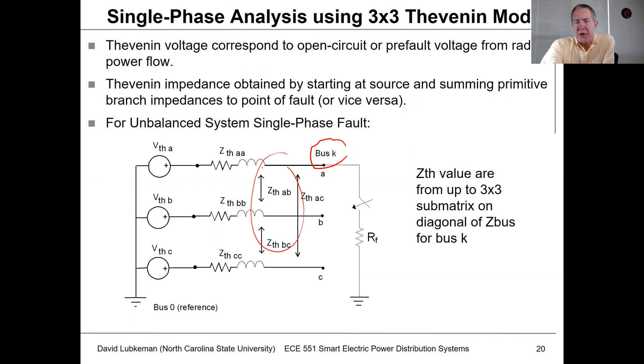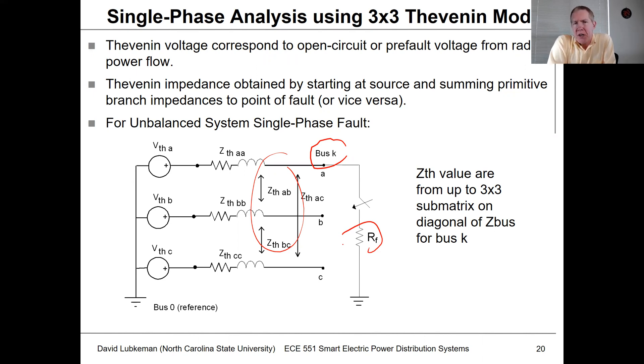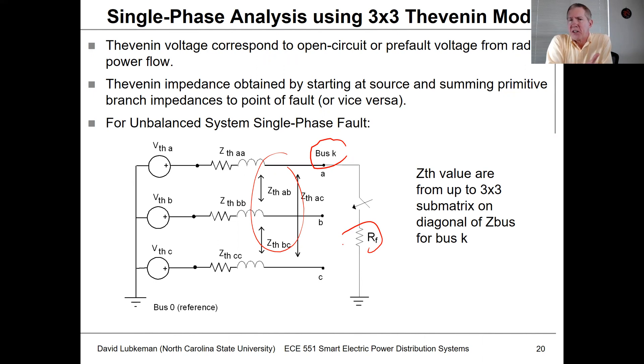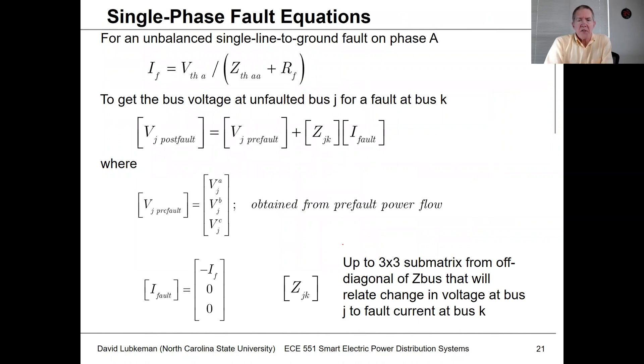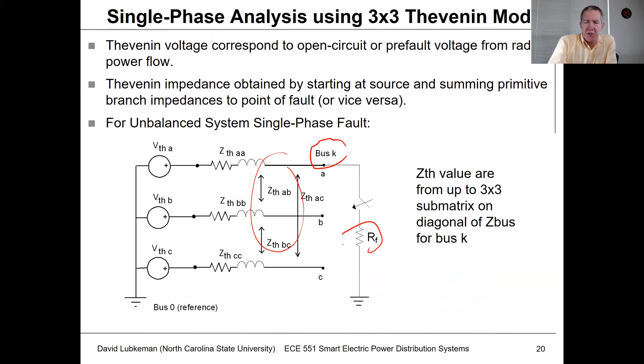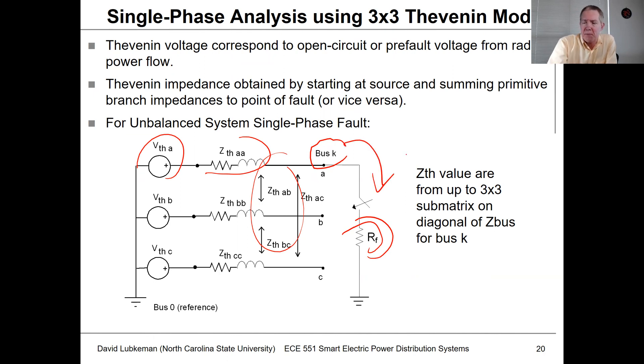For our fault, let's assume we're going to put the fault on phase A, and this fault can have a certain resistance associated with it. This is sometimes useful if you want to model high impedance faults. A lot of utilities will look at a range of fault impedances between zero and 40 ohms, where 40 ohms might be the case where you have a tree limb fall into the line — not drawing a lot of current, but you want to quantify that somehow. To get the value of current, we just take the voltage and divide through by the Thevenin impedance Z_AA plus RF, the fault impedance.